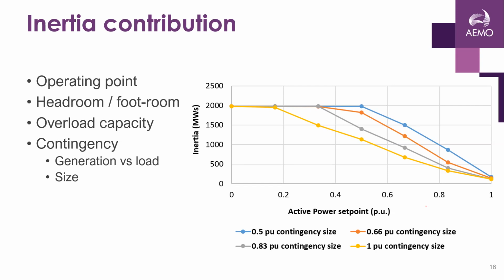As you move towards its maximum operating point, the inertia contribution, which is on the y-axis, is gradually going to reduce. You can see the lines converging towards a very small value. It will depend on the overload capacity and on the size of the contingency. So if you're sitting here and the size of contingency is 0.5 per unit of the rating, you get a different megawatt-second response compared to sitting here.